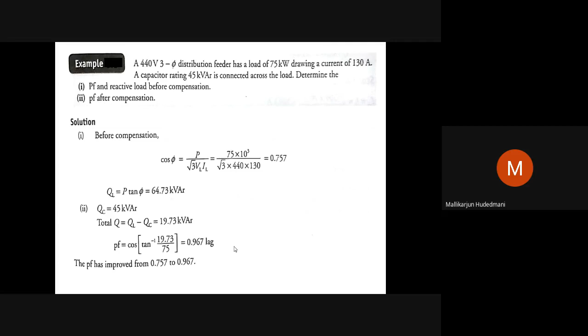The reactive power supplied by a capacitor bank is Q equal to active power inside the bracket, tan phi 1 minus tan phi 2. Hope you remember that triangle where two triangles, one inscribed in the other, the vertical sides are shrunk down, and phi 1 and phi 2 are the angles included by that vector. Then P into (tan phi 1 minus tan phi 2) gives you the reactive power. So this kind of problem you might have solved in UEP.